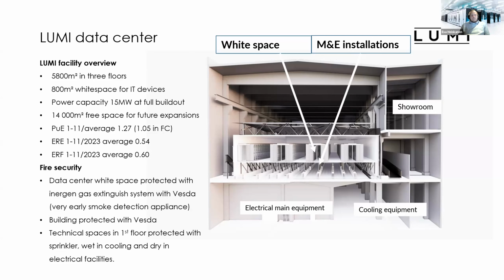About the fire security of the data center, we have this data center protected with the Inergen gas extinguishing system, with Vesta, which is a very early smoke detection appliance. And this whole building is also protected with Vesda. Technical spaces on the first floor are protected with a sprinkler system. So we have the wet sprinkler in the cooling equipment facilities and the dry one in the electrical facilities.